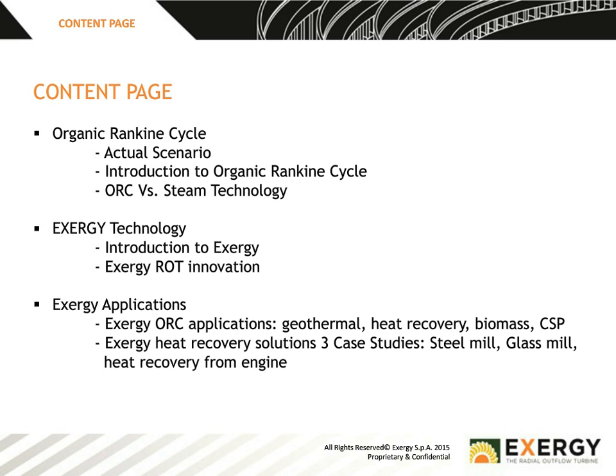So the ambient temperature has an effect on the air cooling system. As the temperature increases, the amount of heat you can dissipate via the air cooling system tends to be reduced. So what you find is that when you have an air cooling system, we design for, let's say, the average temperature of the year. If we look at maybe Northern Europe, I guess an average temperature would be about 8 degrees Celsius. So you can design for that temperature.